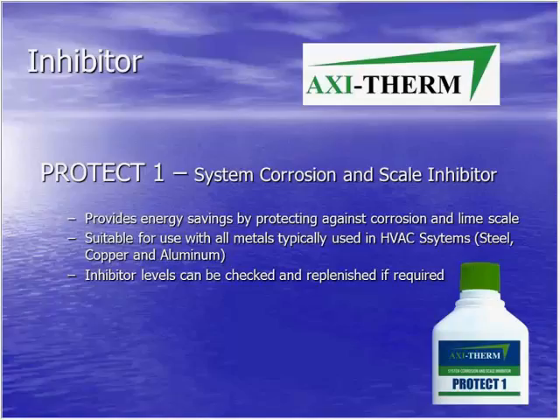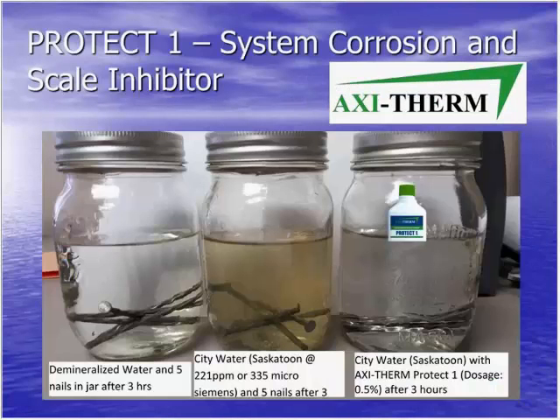This is just a quick photograph that I wanted to show of how the system corrosion and scale inhibitor works. The middle jar there is the five nails in a jar test, just after 3 hours, and that's Saskatoon city water where I'm from. The conductivity level of the tap water at the time was 221 parts per million, or 335 microsiemens. After 3 hours, you can see the corrosion process is already well under way. It's actually difficult to see through.